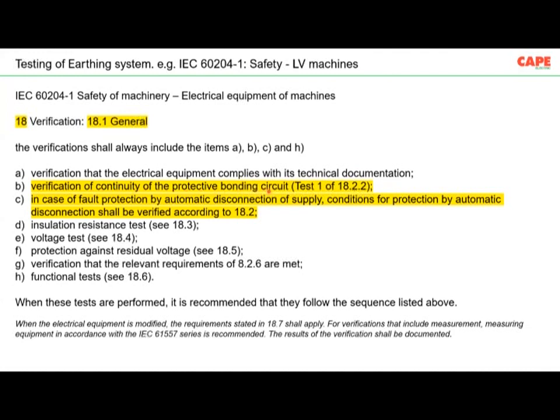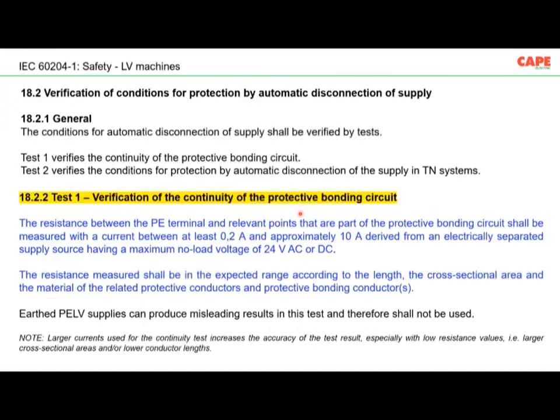Verification of continuity of the protective bonding circuit. So the equipment or the machine is earthed in the sense that the PE terminal of that machine is connected to the equipotential bonding conductor. So the continuity of that earthing conductor, that particular wire, must be tested and ensured. That is earthing. Number two, in case of fault protection by automatic disconnection of supply, the condition of protection by automatic disconnection of supply shall be verified. So the first one, clause 18.2, I will show you what exactly these tests mean.